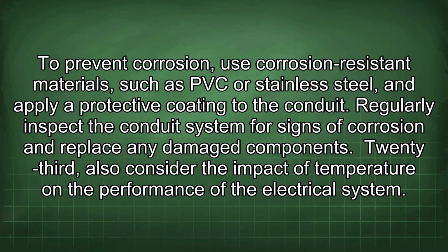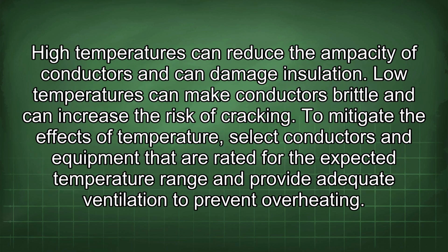23rd, also consider the impact of temperature on the performance of the electrical system. High temperatures can reduce the ampacity of conductors and can damage insulation. Low temperatures can make conductors brittle and can increase the risk of cracking. To mitigate the effects of temperature, select conductors and equipment that are rated for the expected temperature range and provide adequate ventilation to prevent overheating.